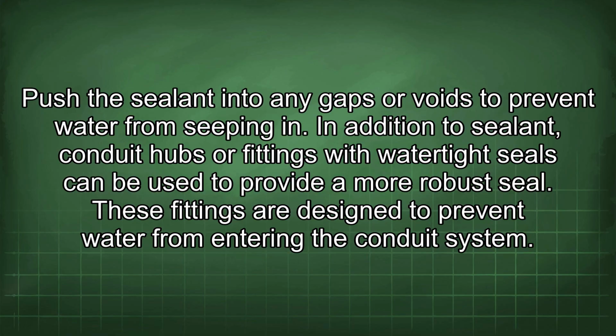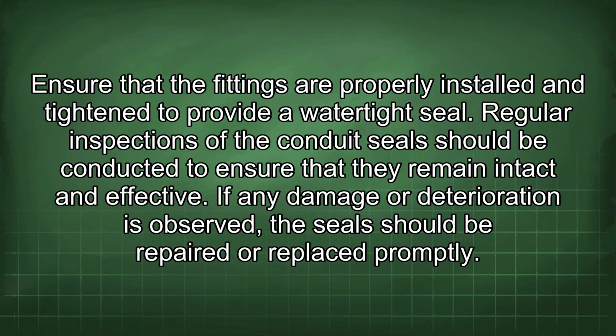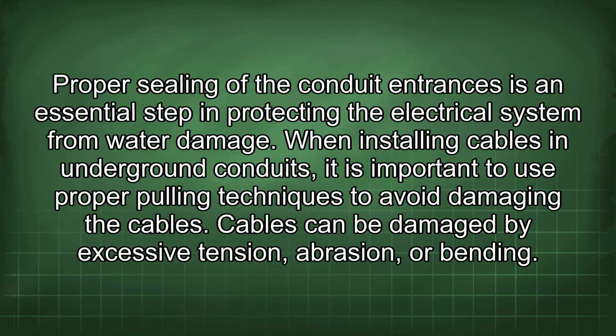In addition to sealant, conduit hubs or fittings with watertight seals can be used to provide a more robust seal. These fittings are designed to prevent water from entering the conduit system. Ensure that the fittings are properly installed and tightened to provide a watertight seal. Regular inspections of the conduit seals should be conducted to ensure that they remain intact and effective. If any damage or deterioration is observed, the seal should be repaired or replaced promptly. Proper sealing of the conduit entrances is an essential step in protecting the electrical system from water damage.